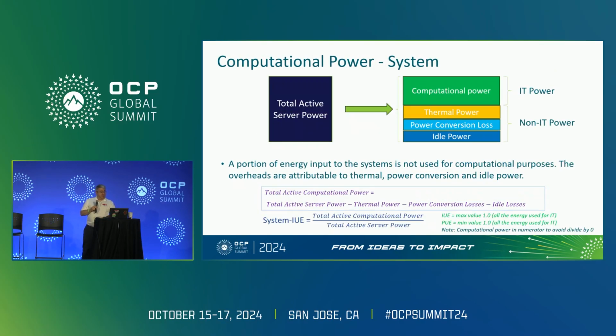So the idea now is to take what was PUE and bring it to the IT level, calling this the IUE, IT utilization. This is a zero-based coefficient: take the computational power, the green box, divided by the total, the dark blue box, and you get a percent. You're trying to drive that up to 100%, or 1.0 would be the peak. There are reasons for having those at different scales, and you can do multipliers and things. And I was told there would be no math.